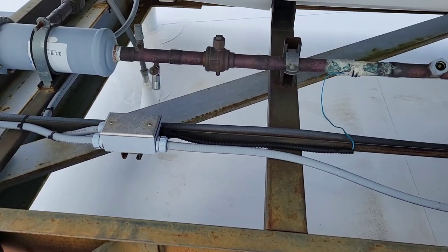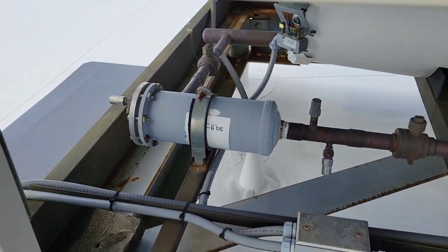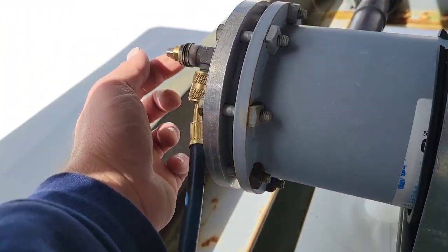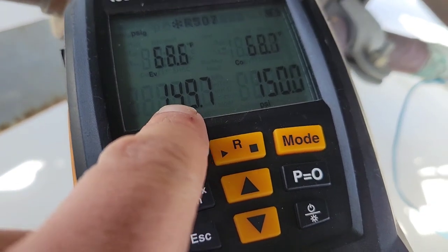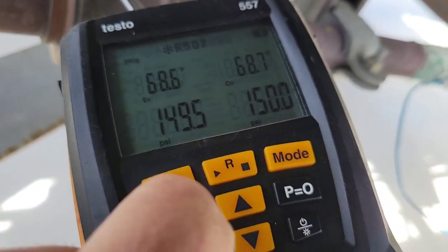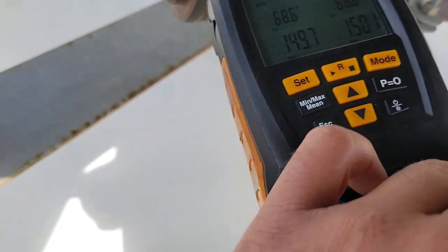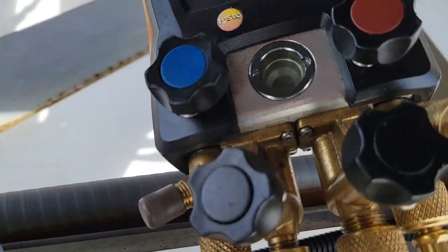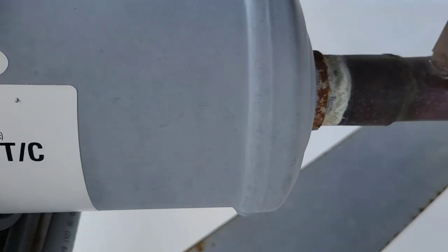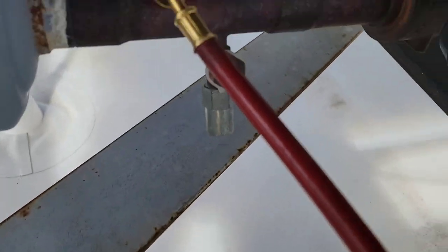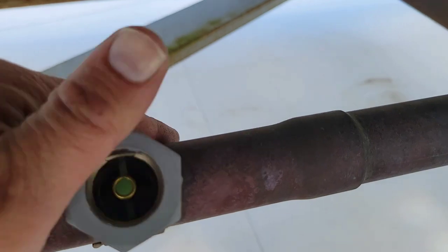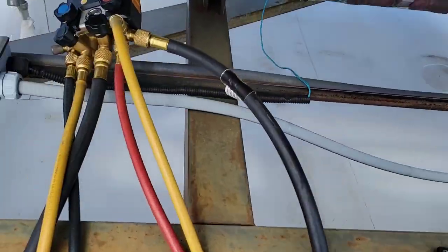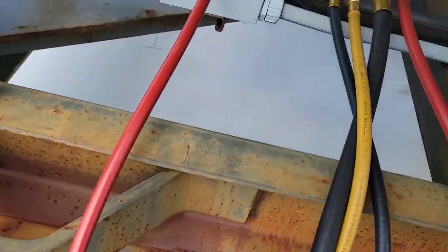So now I'm just going to hook up my gauges quick. We're going to check that filter dryer. This is now hooked up to this filter dryer. I took off these caps, turned that open a little bit, turned this one open a little bit. We're getting 149, 150. Okay, that's nothing. It's like half a PSI. That's fine. It might even be that my gauges aren't calibrated right, or just a delay, but that is perfectly fine. The PSI drop across this thing is almost equal. And if we come over here, even our sight glass has cleared now that more refrigerant has started to flow. While I'm here, I'm also looking at that condenser, making sure it's not plugged, just doing all these little things.